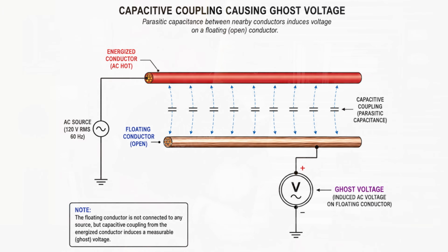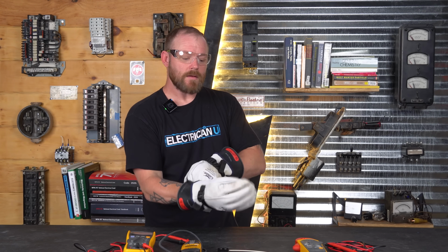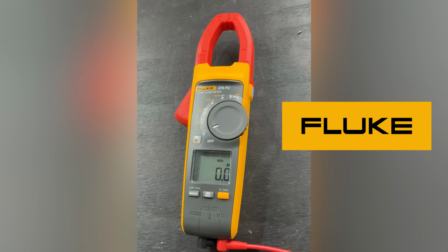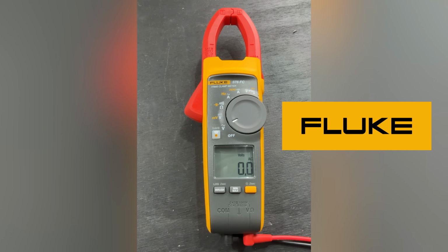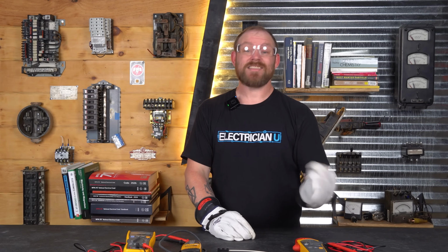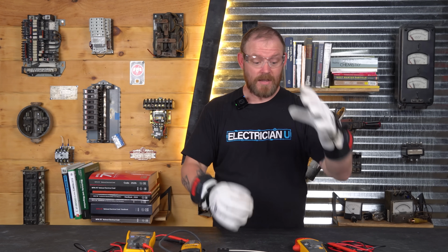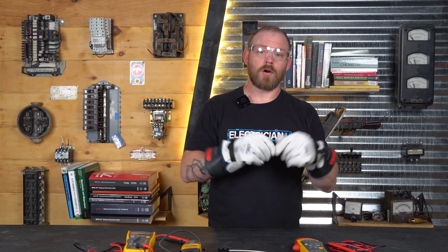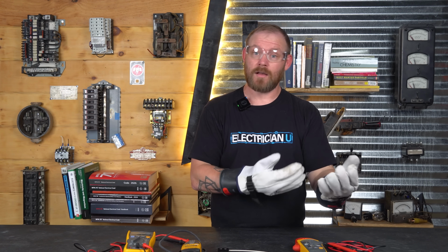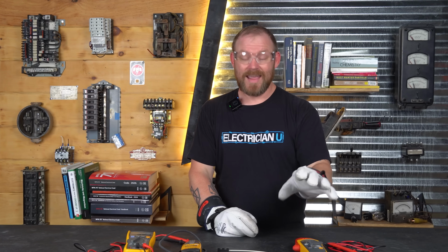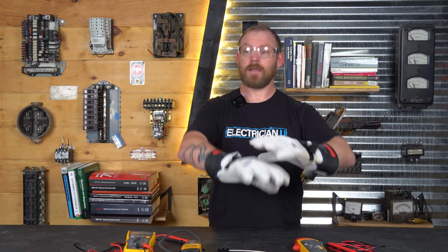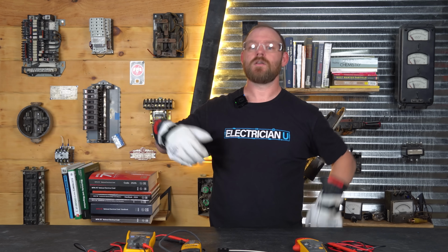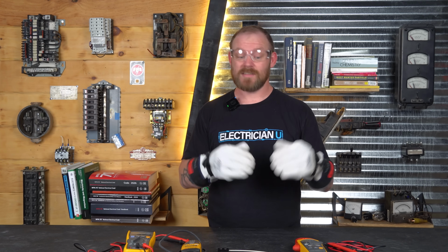For the first one, we're going to use a normal multimeter. This is the Fluke 376 FC. This doesn't have a low impedance mode or a low Z mode. This actually has a high amount of impedance because as a piece of test equipment, you want a lot of impedance, so only a little bit of current has to flow through the thing for it to display values and do calculations for you. So this is a high impedance multimeter like most of the testers. The T5 600 that I have, the T6 1000, all of those are high impedance. They don't have a low Z mode.